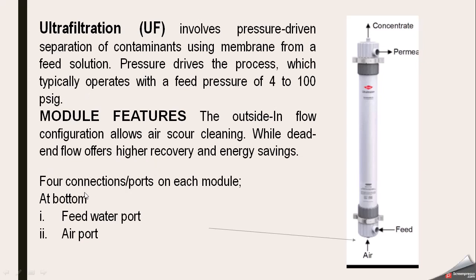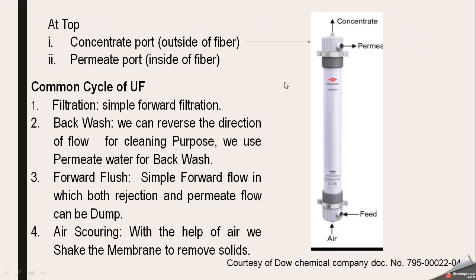There are four connections in each module. At the bottom there are two ports: one is for air and one is for feed. At the top there are two ports: one is for permeate and the other is for concentrate or reject. These are the four ports used in a single module.